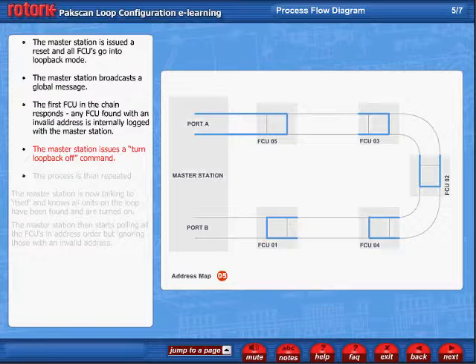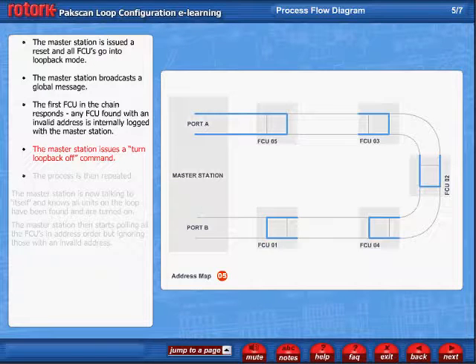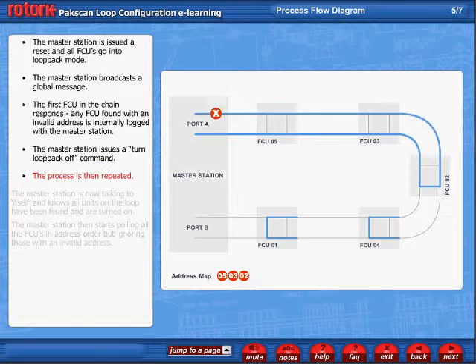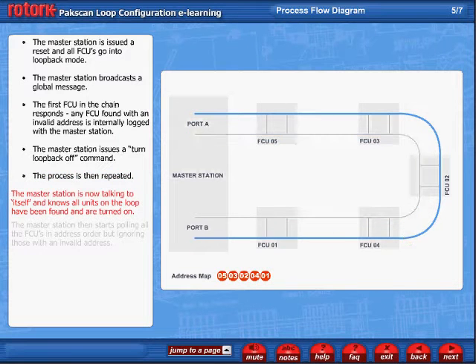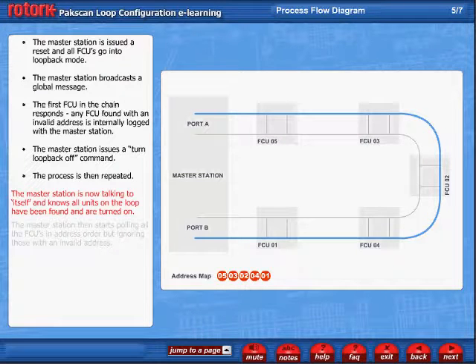The master station then issues a turn loopback off command to the FCU which responded. The process is then repeated until the messages at port A are being received at port B. The master station is now talking to itself and knows that all units on the loop have been found and are turned on.